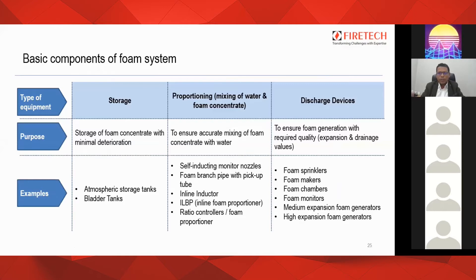The basic components of any foam system consist of three main components: one is storage, second is proportioning, third is the discharge devices. The purpose of storage equipment is to store the foam concentrate with minimal deterioration — that is, disintegration of the chemistry of the foam. Examples of such are atmospheric storage tanks and bladder tanks.